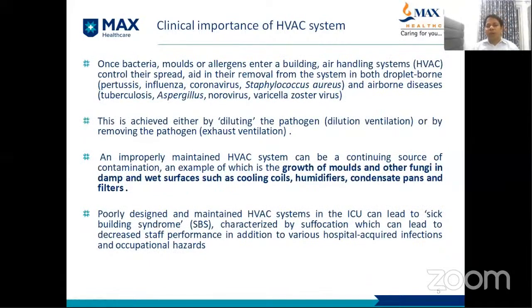Once bacteria, molds, or allergens enter the building, air handling units control their spread and aid in their removal, for both droplet-borne as well as airborne diseases. This is achieved either by diluting the pathogens, called dilution ventilation, or by removing the pathogens, called exhaust ventilation. An improperly maintained HVAC system can continually be a source of contamination, for example growth of molds and other fungi on damp and wet surfaces such as cooling coils, humidifiers, condensate pans, and filters. A poorly designed and maintained HVAC system in the ICU can lead to sick building syndrome, characterized by suffocation, which can lead to decreased staff performance, in addition to various hospital-acquired infections and occupational hazards.